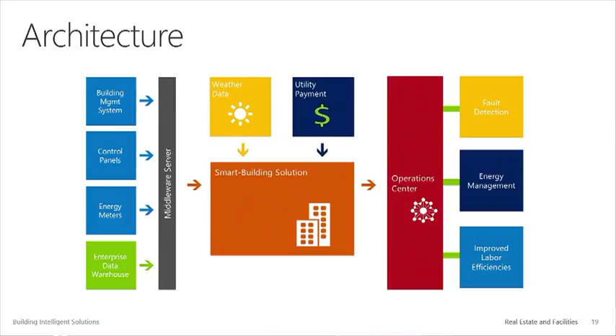So this is the network architecture from a high level. If you think of it, it's building management systems. We have seven. We go down to control panels, energy meters. We consume data from buildings that are two years old, buildings that are 35 years old. Everything we're doing here, there was not any hardware installed, there were not any sensors installed. This is a completely software play. We're using the operational data that's coming out of the systems as they were built, as they were put in the buildings, to optimize them.